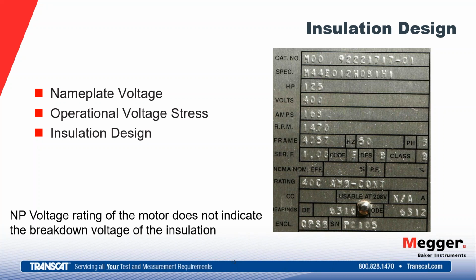So it will be higher, especially initially when a motor is first manufactured. At its breakdown voltage, the insulation can no longer withstand the stress across it. The resistance will actually drop to zero, and a significant current is allowed to flow through the insulation material. That's what happens during breakdown. However, the breakdown voltage is a separate rating from the operating voltage of the insulation. So the insulation is designed to withstand a significantly higher voltage than its operating voltage. So we have to design this motor in such a way that its breakdown voltage is much higher than the applied voltage.